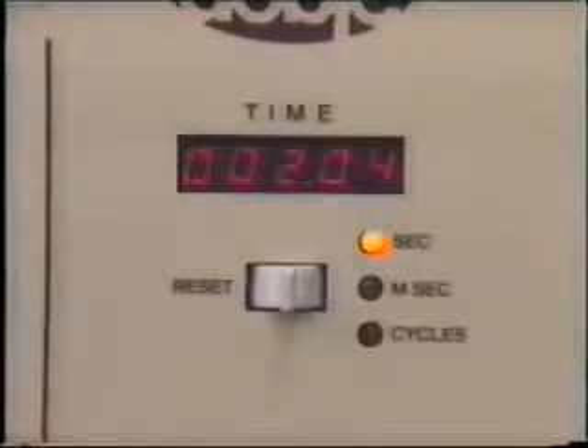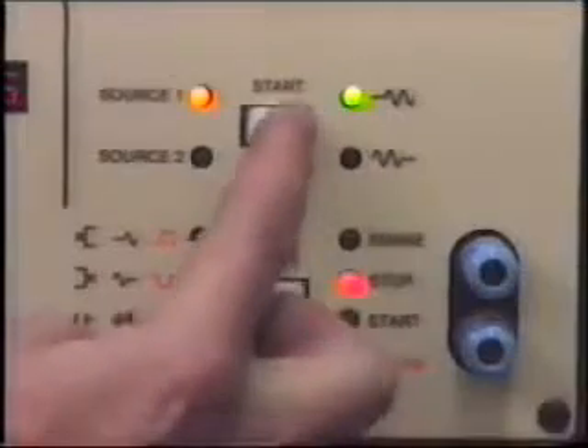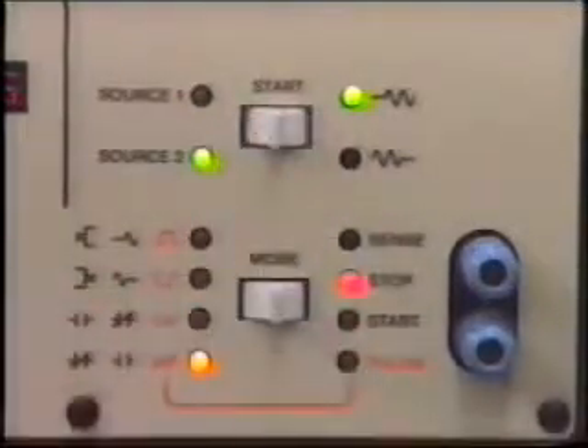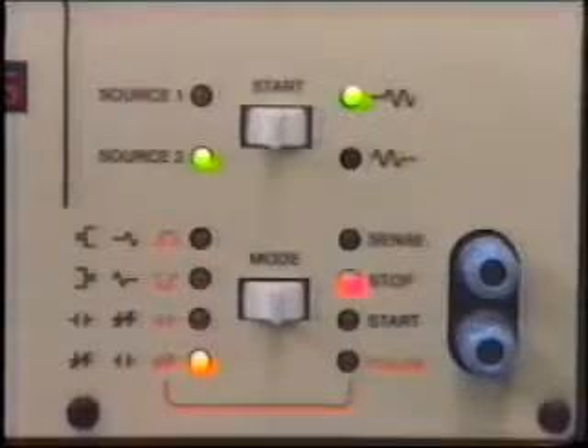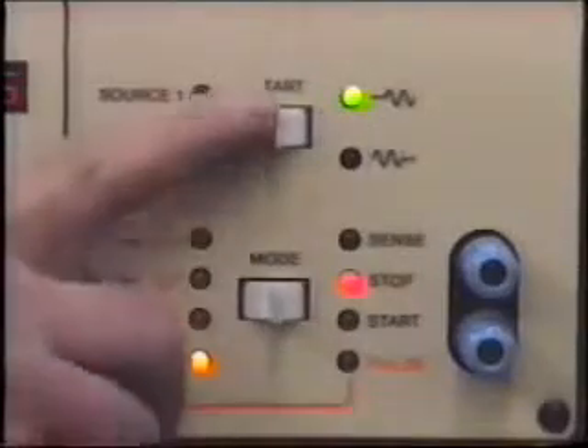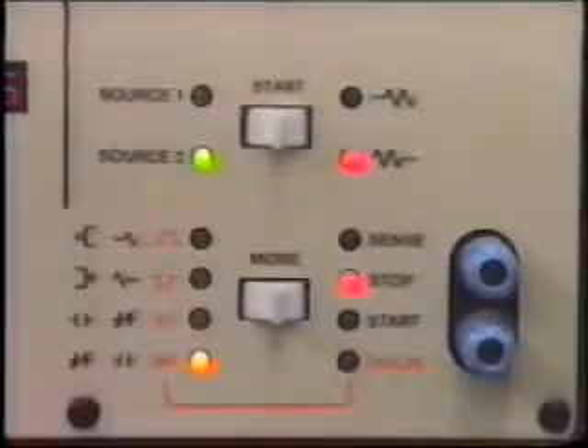Finally, we arrive at the timer section of the panel. This reset switch resets the timer to 0 after a test. This switch, to the left, selects source 1 or source 2 as the timer start. To the right, it selects source off to on or on to off for timer start. The bottom switch selects the timer stop mode.